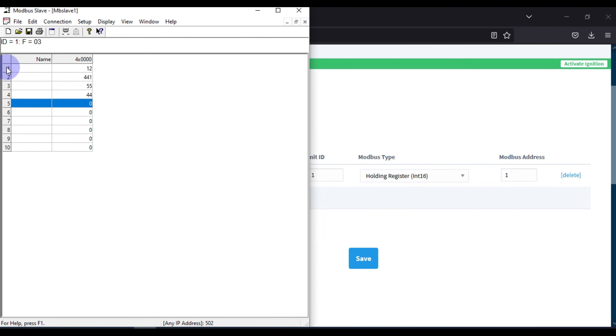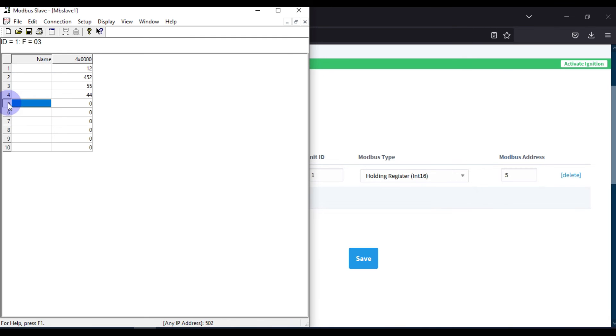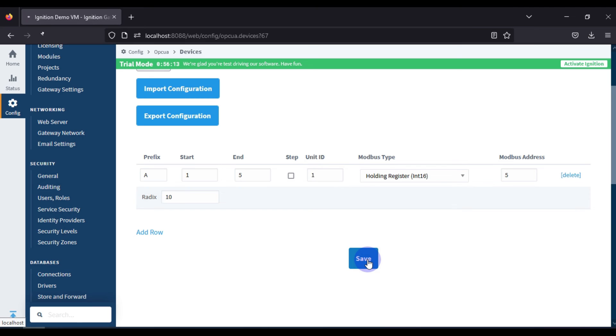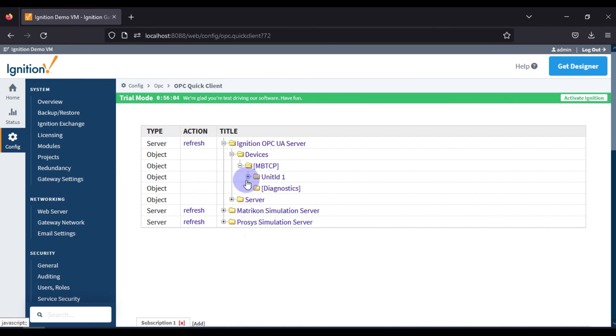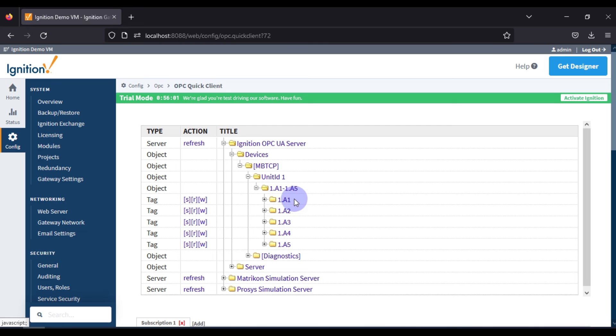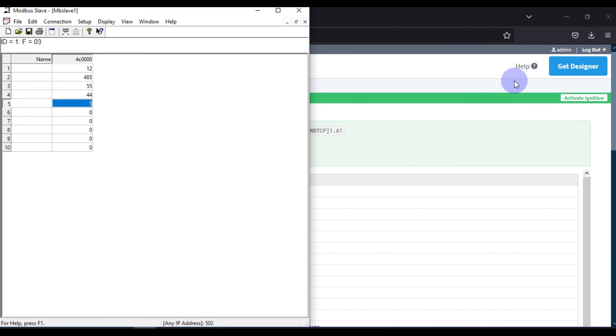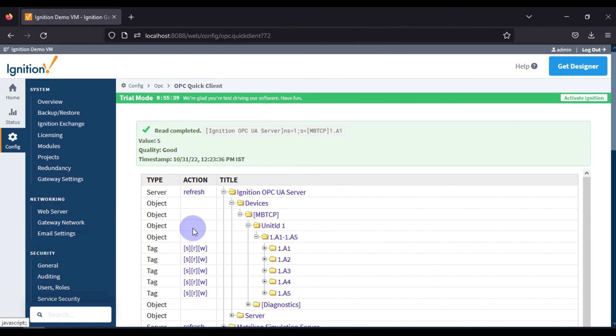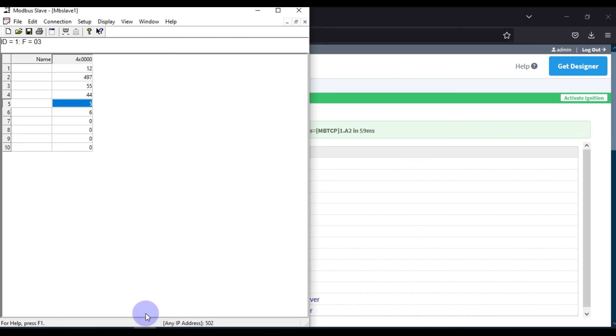Here you can also see the Modbus address field. We specified Modbus address 1, so it reads from 400001. If I write 5 there, Ignition SCADA will start reading from address 400005. After saving and going back to OPC Quick Client, the tag names are still A1 to A5 but they now map to addresses starting at 400005. Writing to the 5th tag address 400005 and reading confirms the value 5, and writing 6 there gives value 6 at address 400006.